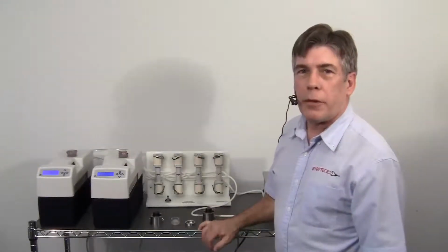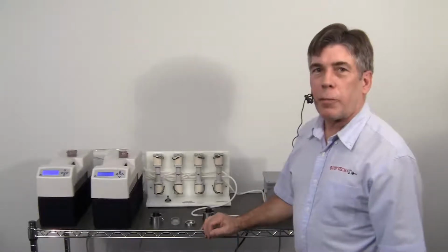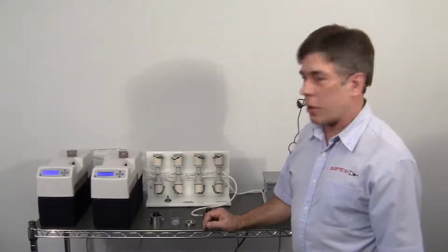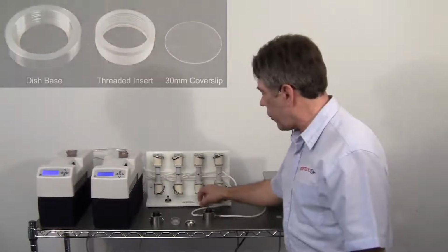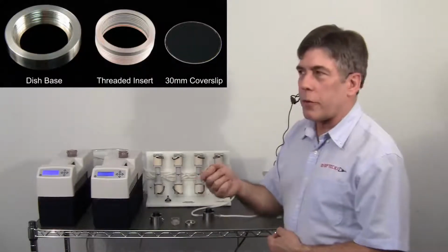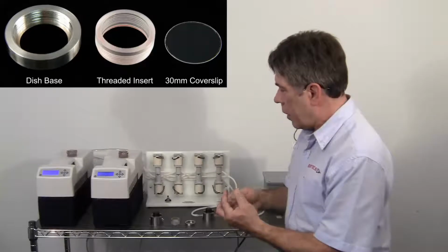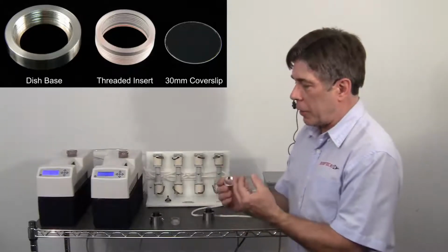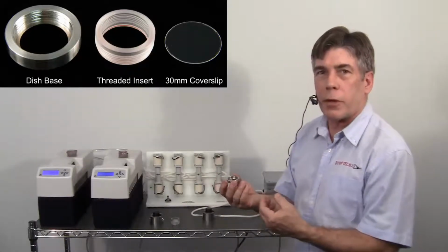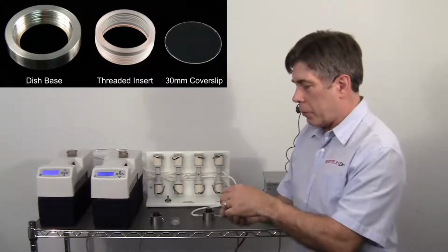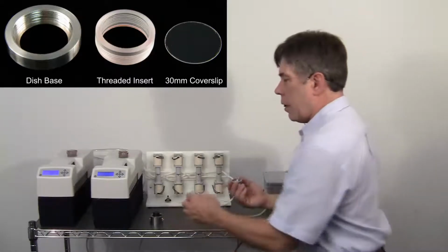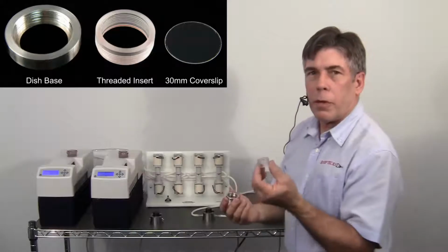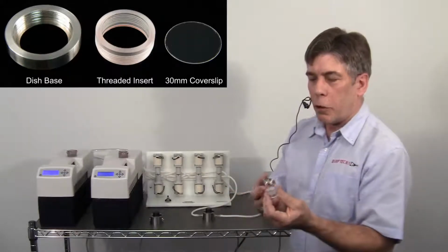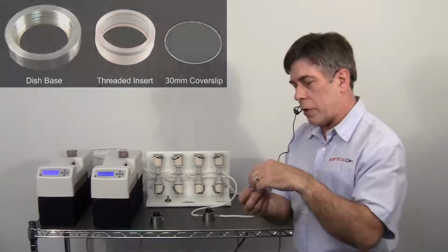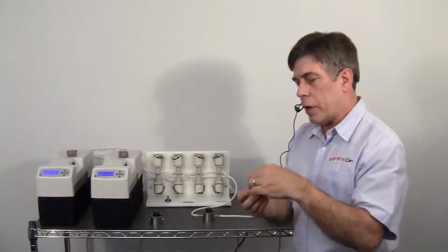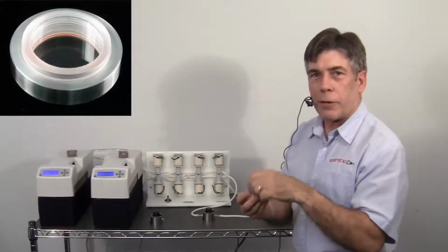In order to accommodate the high numeric aperture objective, the specimen is going to have to be placed onto a cover slip. Now here we have a 30 millimeter number 1.5 cover slip. This cover slip sits into a Bioptechs ICD, which stands for Interchangeable Cover Slip Dish. The cover slip simply rests in the bottom of the dish, and then an autoclavable polycarbonate O-ring sealed sleeve screws down on top of the cover slip so that you've now made a chamber, basically.